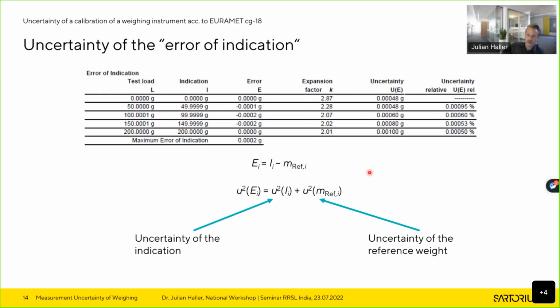Even if you are not familiar with the GUM and how to calculate and determine measurement uncertainties, it is quite straightforward: if you consider that the error of indication is calculated from the indication and the reference weight, then the uncertainty of the error of indication is logically calculated from the uncertainty of the indication and the uncertainty of the reference weight. Why that is squared here, for example, is given in the GUM. So if you are interested in the detailed formulas, please, as mentioned, have a look at the GUM.